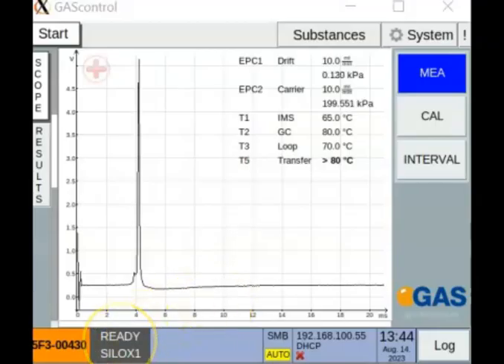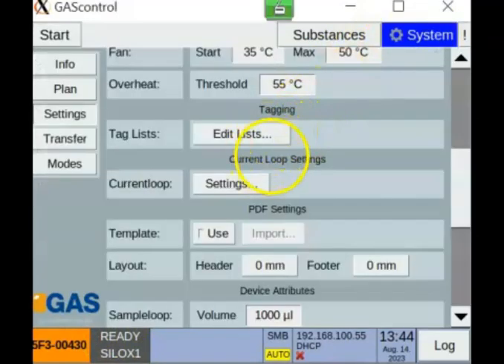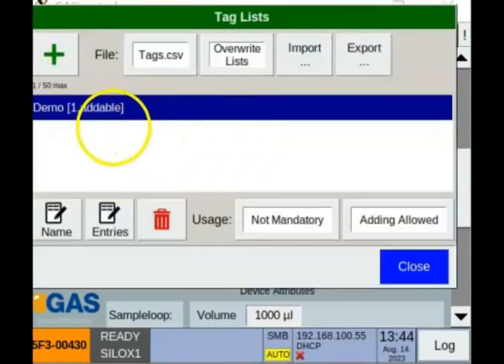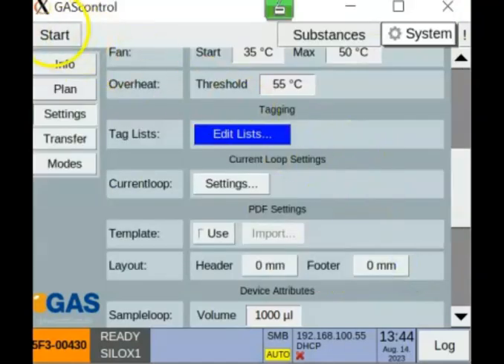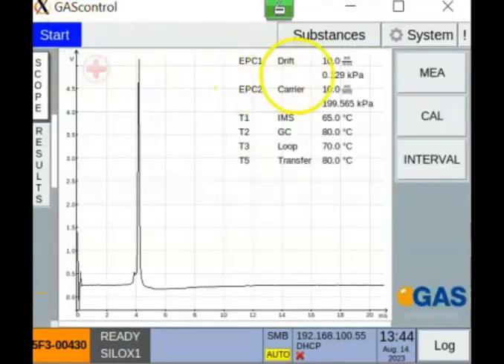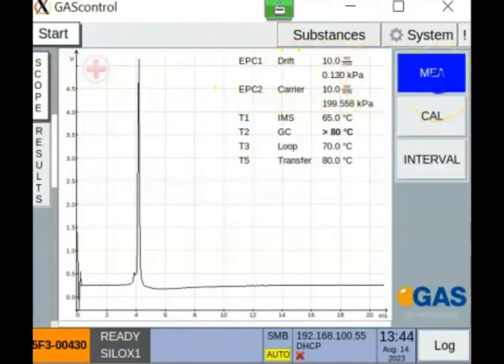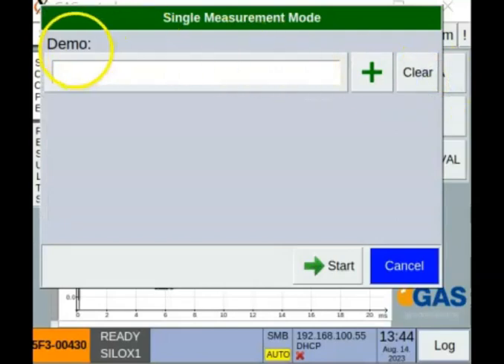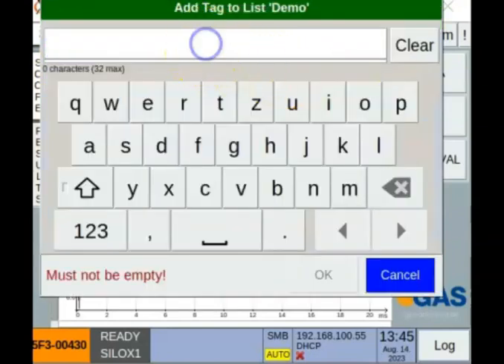The system is ready to do a measurement. In the system, there is the possibility to edit a tag. There is one demo tag available at the moment, and we can go to the start screen and start a manual measurement. The demo tag offers to add new items. For instance, the concentration, which is currently set on the calibration oven.